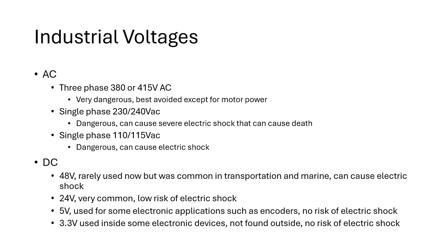So that brings us down to DC circuits, where it's a direct current. So we don't get the alternating current now. What we do is we convert via the industrial power supply, which we've covered. That effectively chops up the AC voltage and converts it into a static DC voltage using a switch mode arrangement. In modern power supplies, we use switch modes. In older power supplies, we might have used a transformer with a bridge and capacitors, but modern power supplies do that via electronic switching technology.